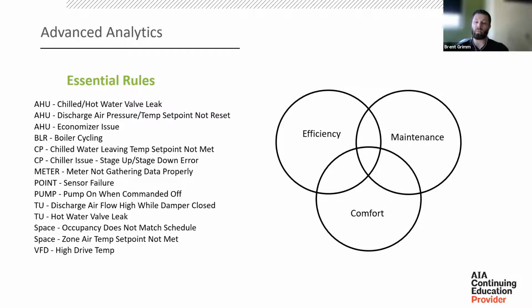One of the things you'll notice is that these rules are not squarely focused on energy efficiency. In fact, some of the issues that can be uncovered can result in more energy use. In some cases, analytics identify rooms that are not meeting set point. Maybe it's because of a seized hot water valve or a plugged screen. But we definitely still want to identify these issues and get them fixed, even though it's going to mean a slight increase in energy usage.